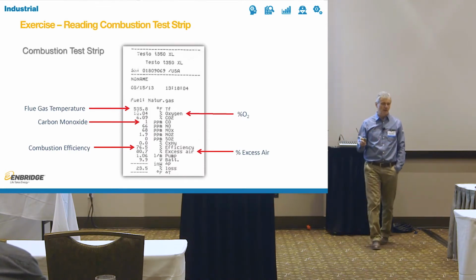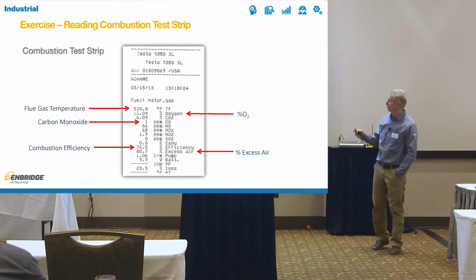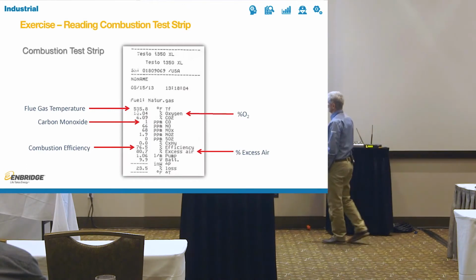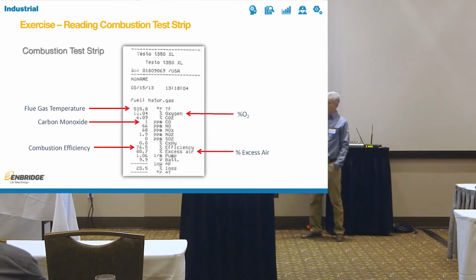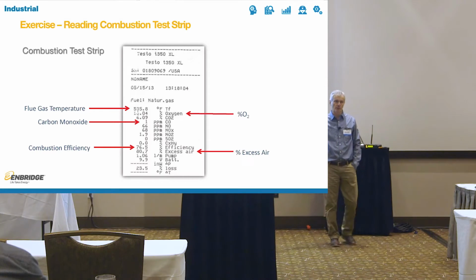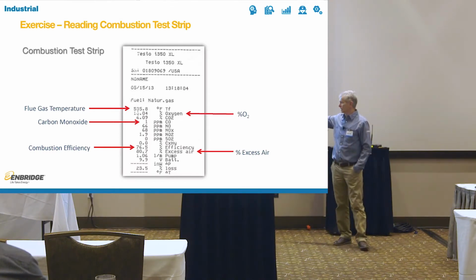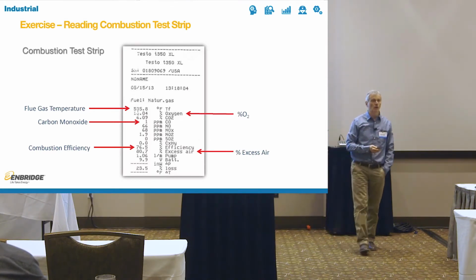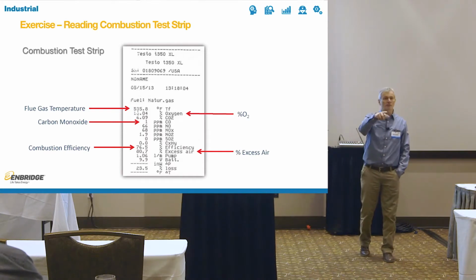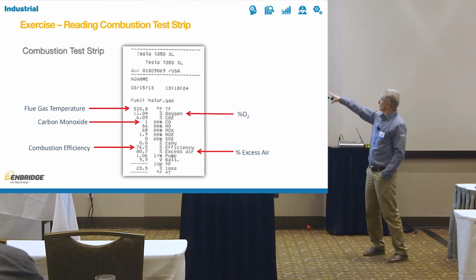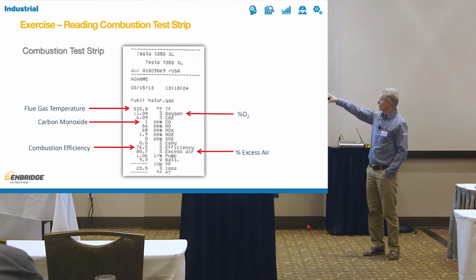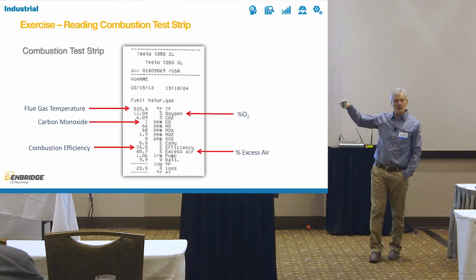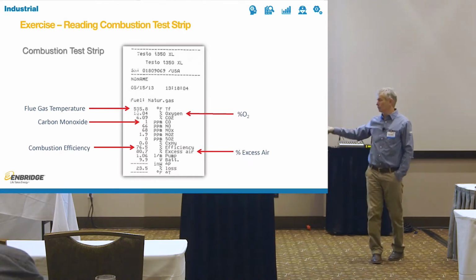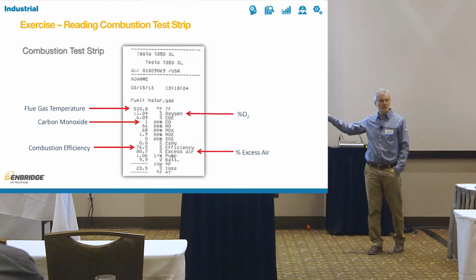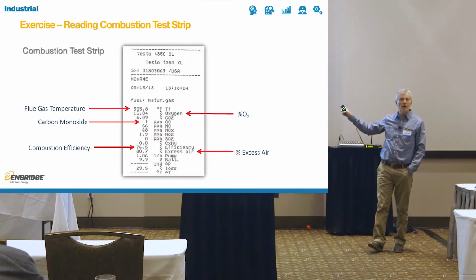Now, there's a big warning that I would put. Unless this instrument was calibrated properly, operated properly, maintained properly, I would not trust combustion efficiency at all. I would use the chart that we gave you. You take the temperatures, you take the oxygen levels, you will get much better results if you look at the chart than you would get from these strips for efficiency alone.